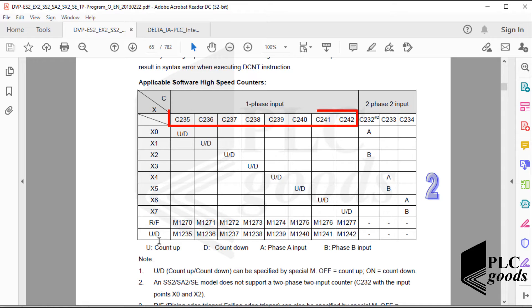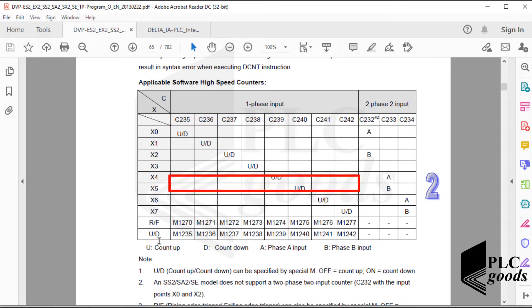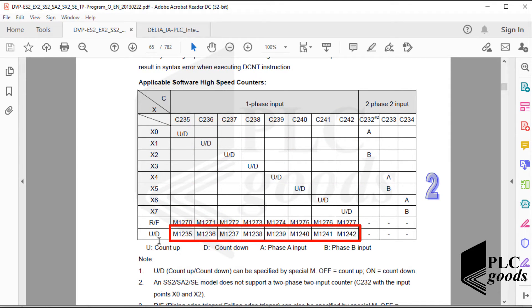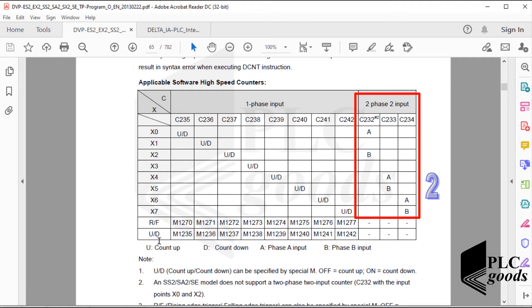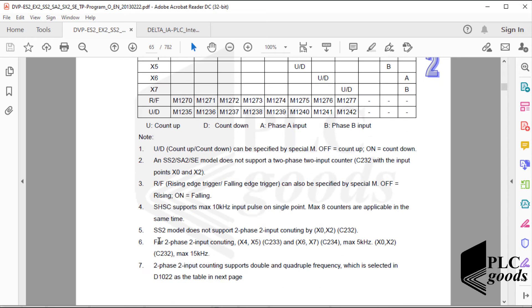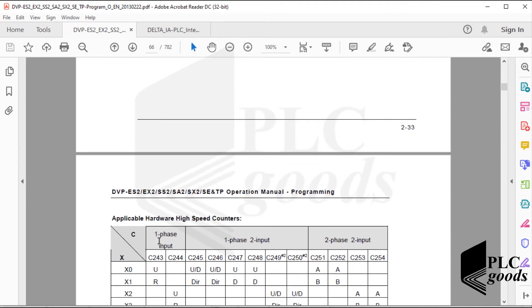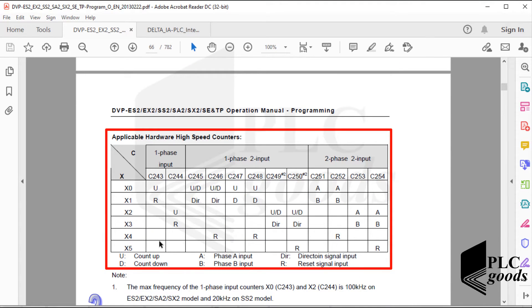These counters can count in two directions, which can be specified by their associated addresses. Also, these addresses determine whether counters must work based on rising or falling edges of signals. Note that some counters use two digital inputs and work differently. Now let me explain hardware high-speed counters — as you can see, hardware high-speed counters work based on two or three digital inputs.